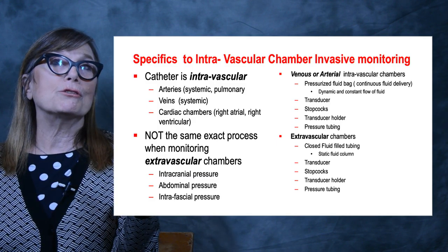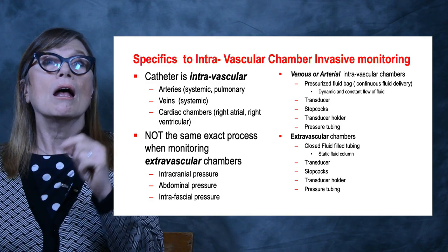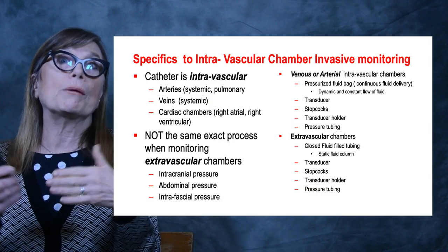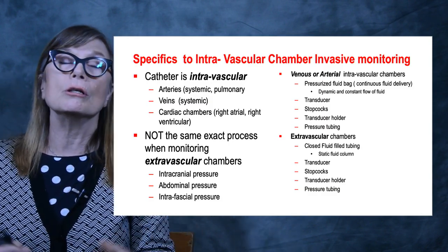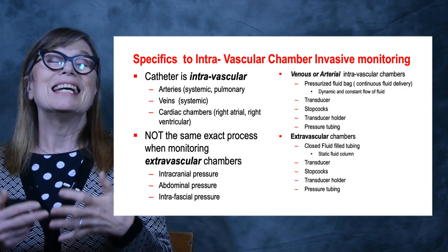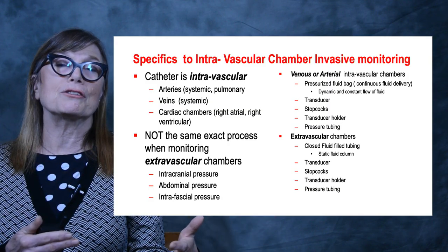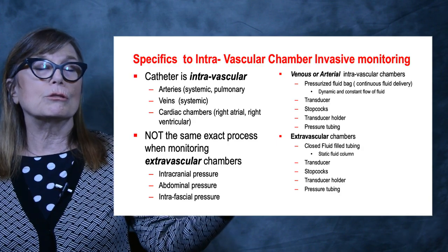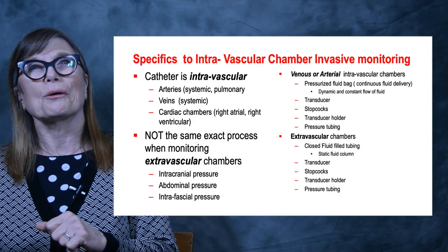At the transducer, we have a series of stopcocks. Those stopcocks, and frequently there's one, sometimes there's two, those stopcocks allow us to actually zero reference our transducer, and our transducer is held in a transducer holder.